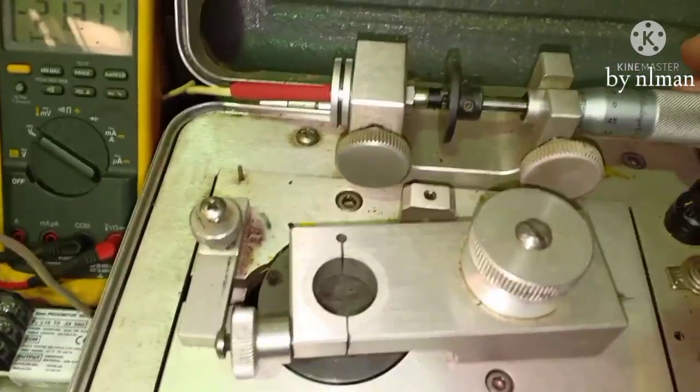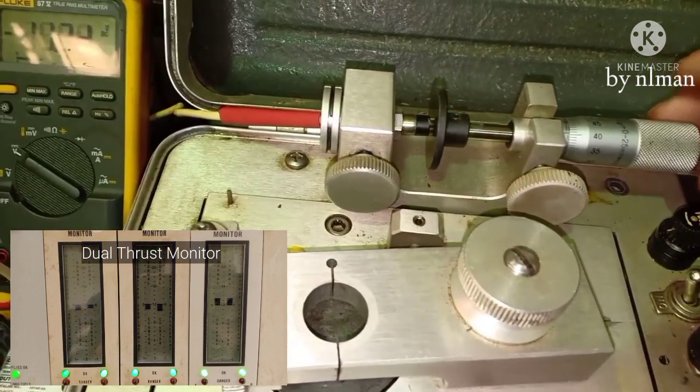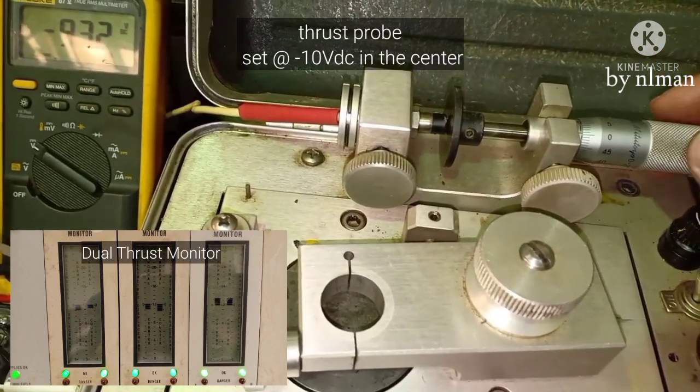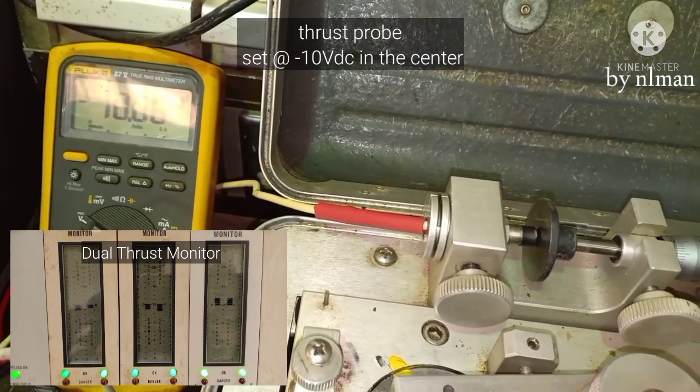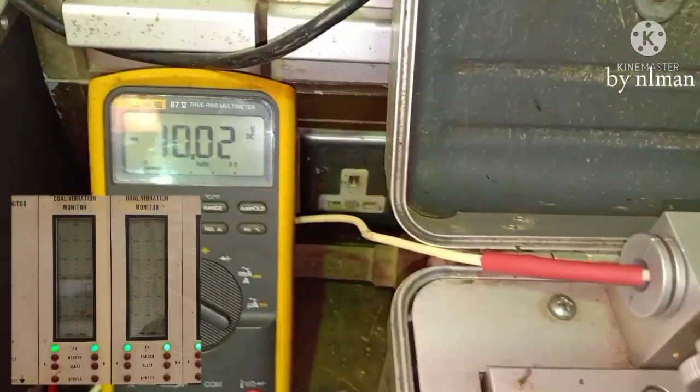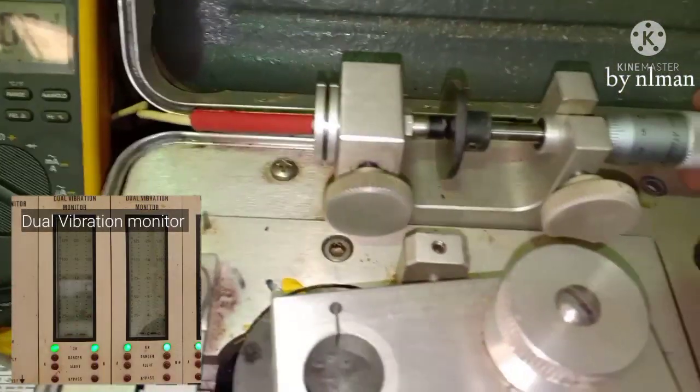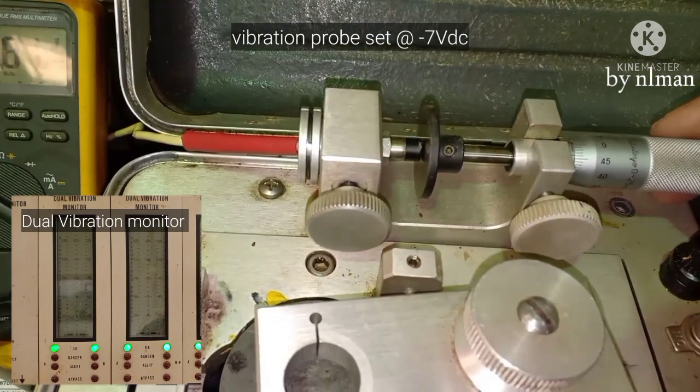So normally, for a thrust probe in the field, we set the thrust probe at 10 volts middle, in the middle, okay. So for vibration normally we set the probe at negative seven.